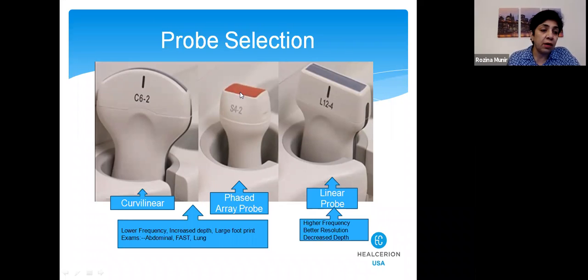Below this, there are a lot of crystals. There are thousands of crystals under this padding. These crystals are responsible for making the images, and they have a piezoelectric effect. I'm not going into the detail of that. The probe which has a curved footprint is called the curved or curvilinear probe. And there is always a frequency written on the probe. For example, over here it's curved 6 to 2. So the highest frequency is 6, and it can be brought down to a frequency of 2.